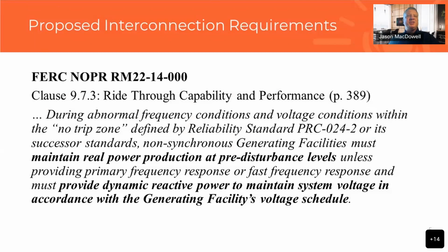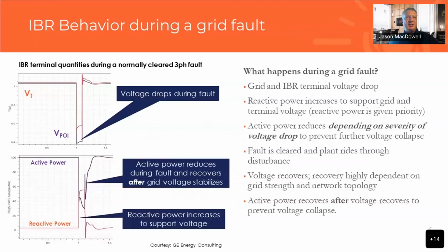So I wanted to just pull on a couple of these in terms of harmonization of language with some of the other requirements. One of the things I think is challenging with calling out the real power to be left at pre-disturbance levels. I think the intent of that was certainly to avoid what we all know has been happening in certain disturbances that happened since 2016 around the U.S., California, and more recently in Texas, called momentary cessation, where there is a blocking or a total reduction of total current into the grid upon a fault.